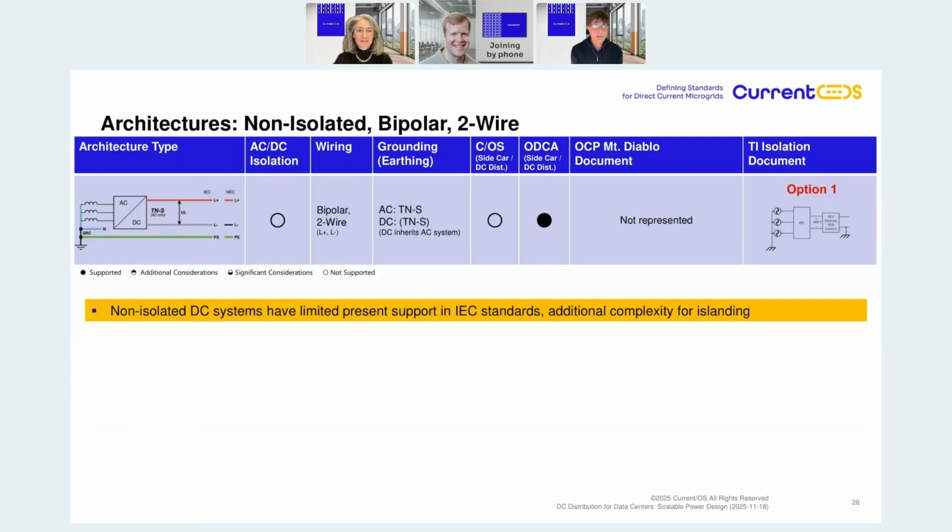And this one is another architecture, the non-isolated converter. Then you have the two voltages against PE, so you have a symmetrical system. This sounds easy, but it has drawbacks. This is not completely validated in CurrentOS, but it is validated in ODCA, and it's mostly for industrial use. The big drawback of these kinds of architectures is that you have a lot of EMI in the system that is distributed through all the power racks. So you have work to do there. And it is very difficult to scale to higher voltages because you are linked to the mains.